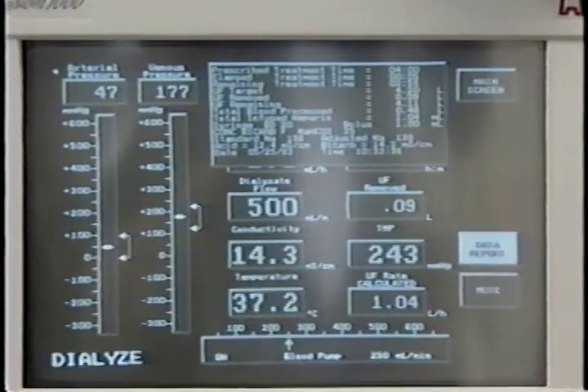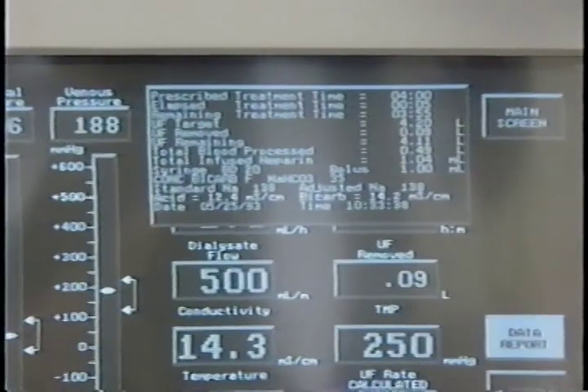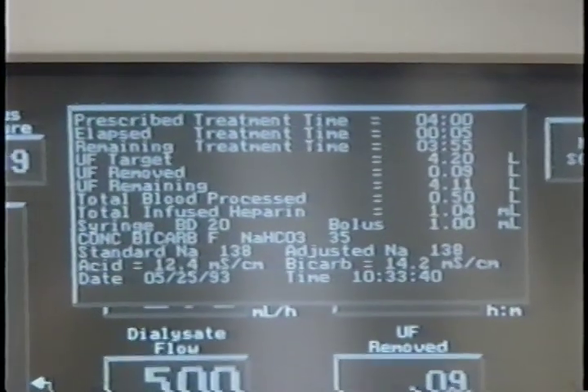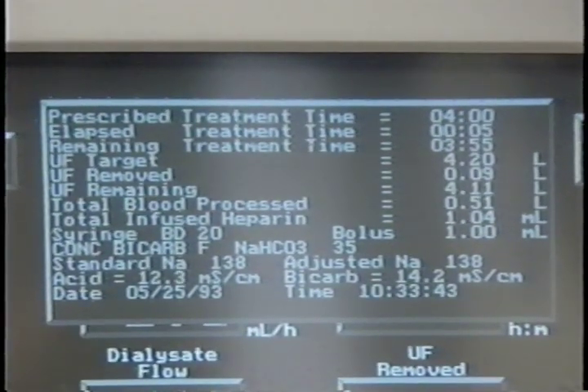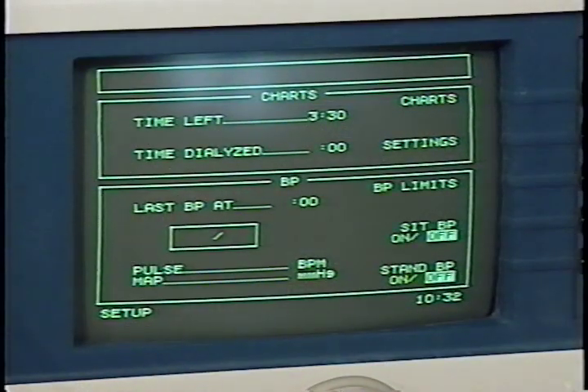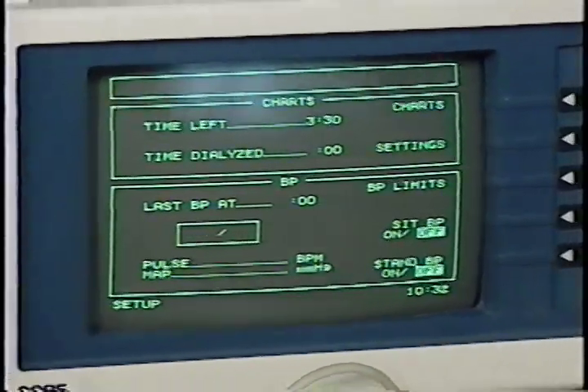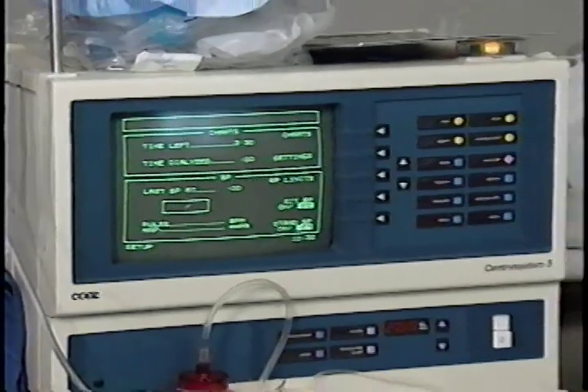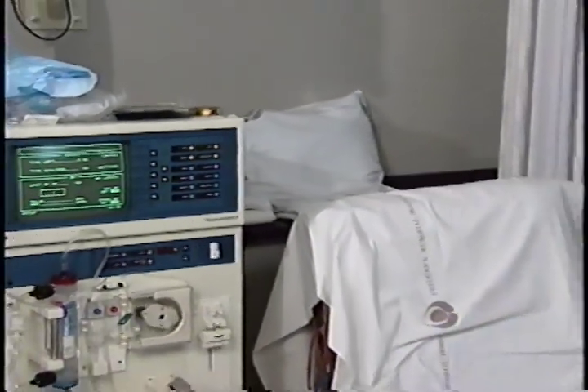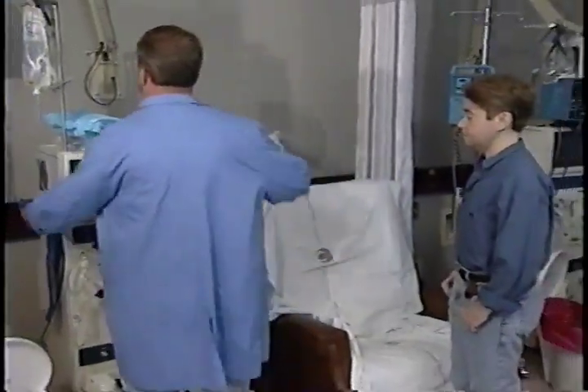The most effective way to determine actual dialysis time is with the use of a machine clock that runs only when dialysis is taking place. Some machines visually display this number. The clock will not run when there are machine alarm conditions that cause an interruption in blood or dialysate flow.